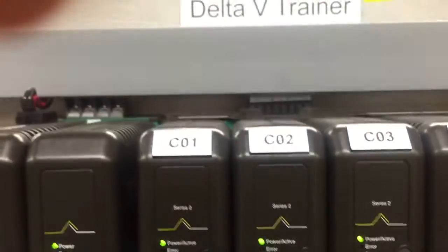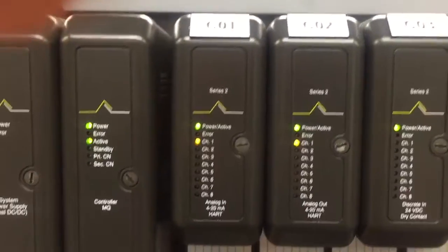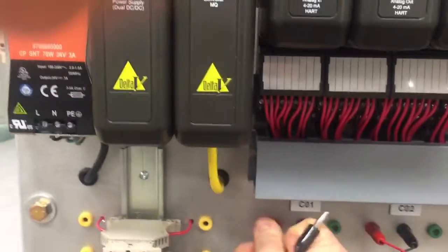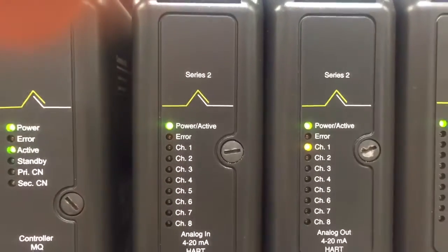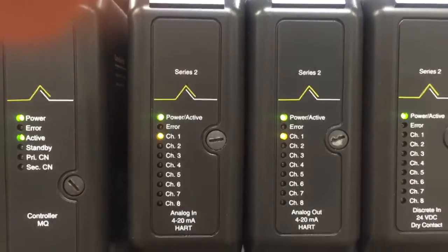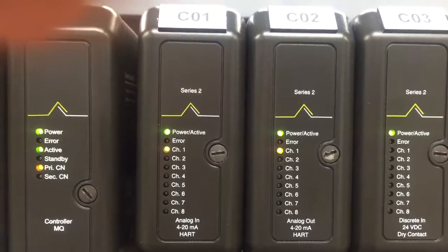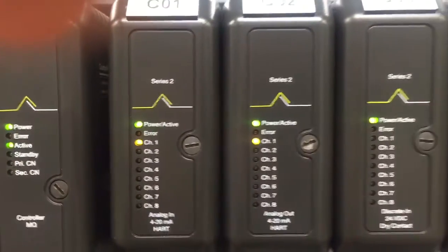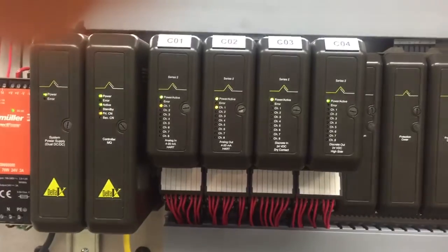If we go over to our control system, you can see channel 1 on both card 1 and card 2 are lit up. You can see that we already have them wired in. If I was to unplug or disconnect our level transmitter, you can see channel 1 starts to flash. So this is nice for troubleshooting. It indicates an open loop on that device. So we'll go ahead and plug this back in, and we'll see that channel light stop flashing, indicating that our loop is now closed.